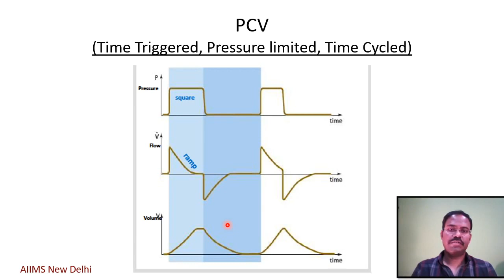So this becomes a time cycled ventilation mode, where the constant pressure will be maintained till the end of inspiratory time, and the flow descends till the end of inspiratory time. During this time, the volume delivered will depend on the patient's compliance and resistance. So the pressure control mode becomes a time triggered, pressure limited, and again time cycled ventilation.